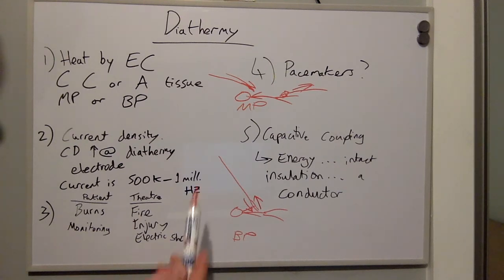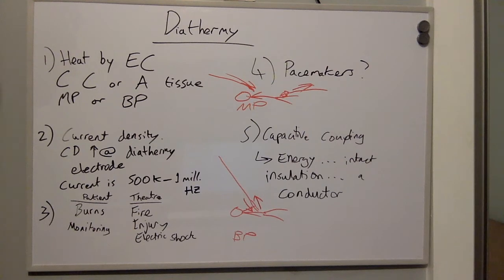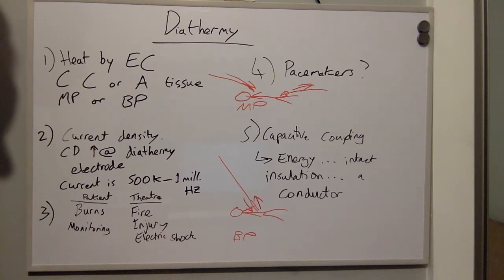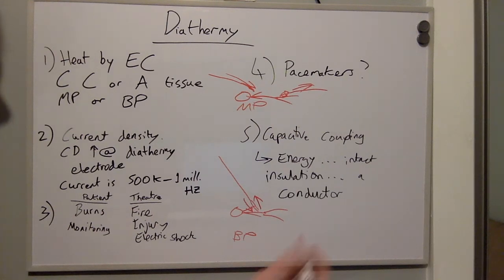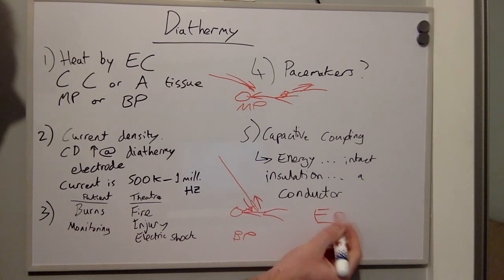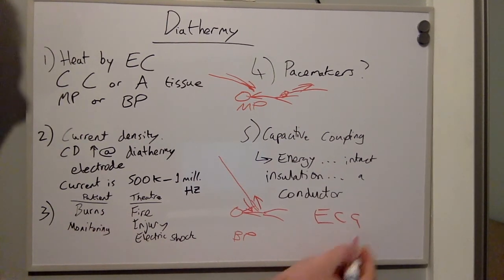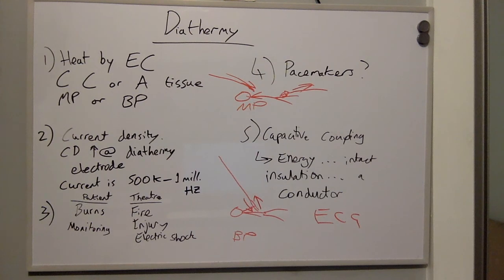What is capacitive coupling? Capacitive coupling describes energy that is transferred through intact insulation to a conductor. The significance of this can be interference to the ECG when a diathermy wire overlies an ECG wire.